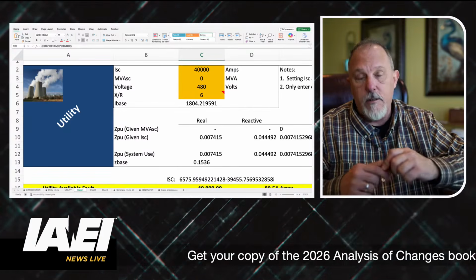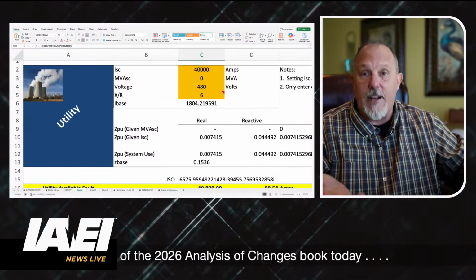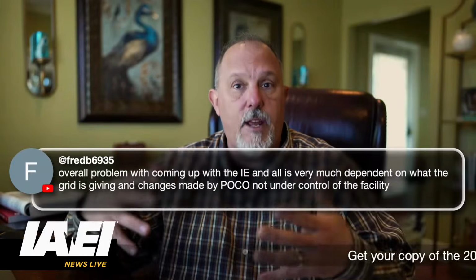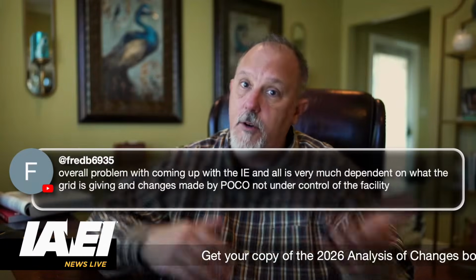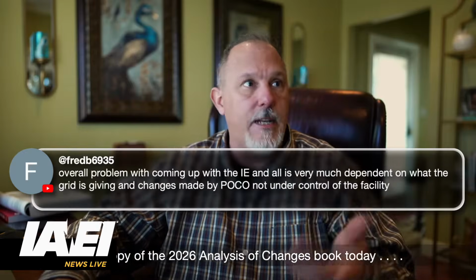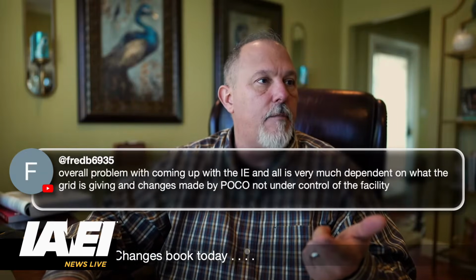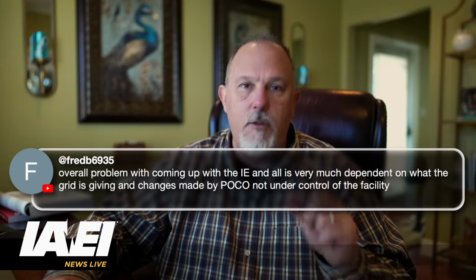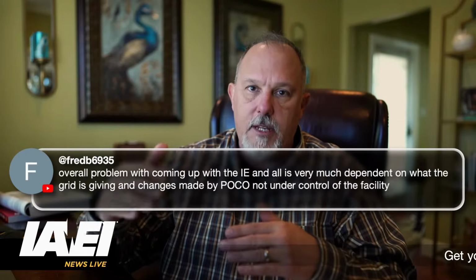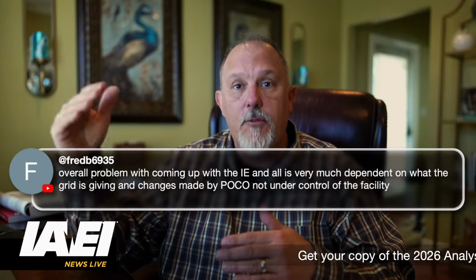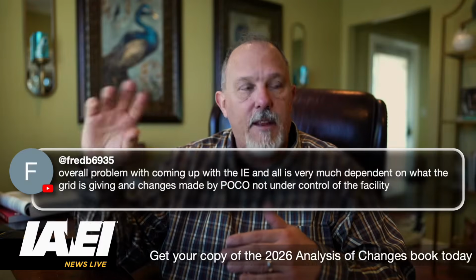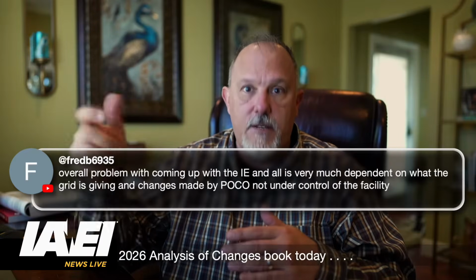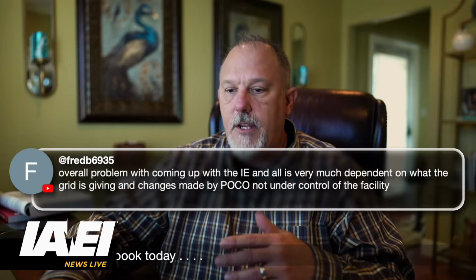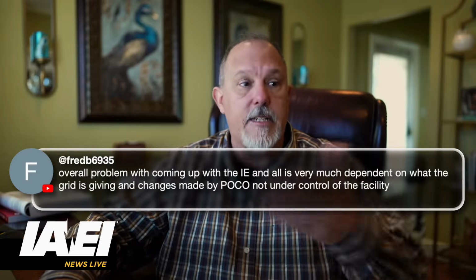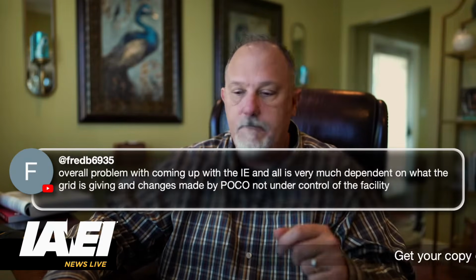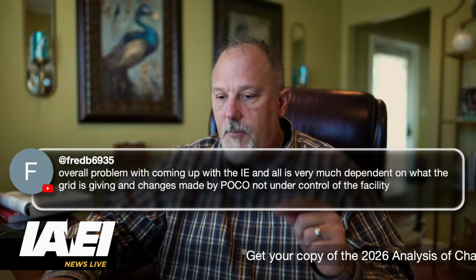Now, from an arc flash perspective, you've got to think about everything that happens. Lower fault currents can make more of a difference in incident energy for sure. But I would say, there's an IEEE document that talks about how to deal with it when they don't give you the actual available fault current, and fluctuations should not be in the tens of thousands of amps, because then you have other issues with short circuit current ratings and interrupting ratings and all that jazz.